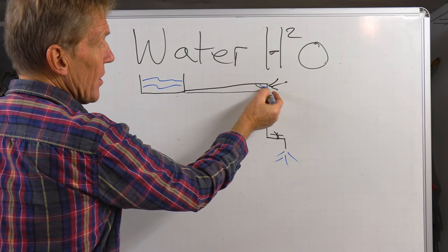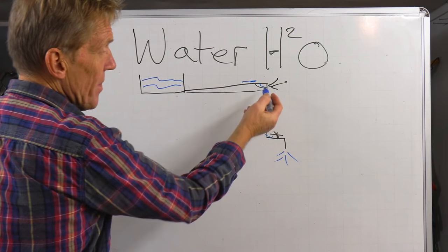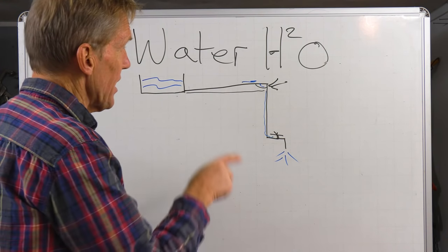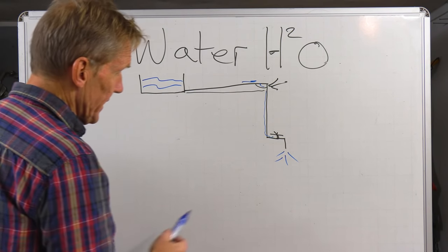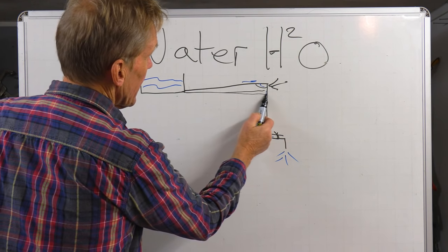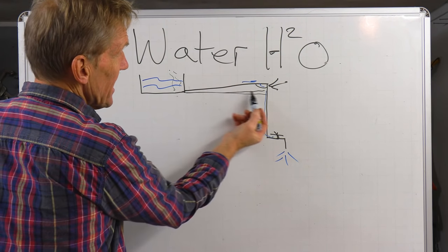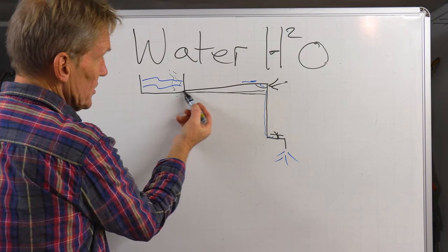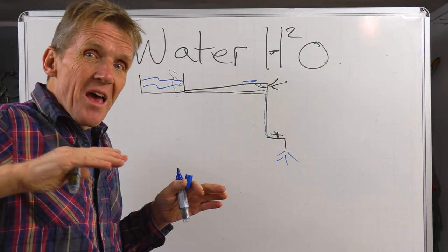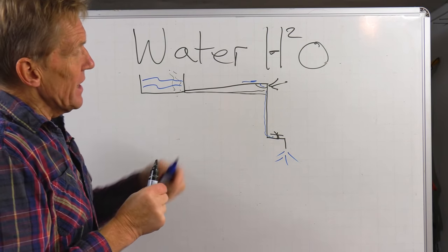But whatever it is, we have this little airlock here. So we've got water here. We might even have water there, but that water can't come out of a tap for exactly the same reason as I showed you in the glass. So the way we get round that is we put that pipe in so that any air in it vents towards the tank and just bubbles up out of there. Now, that means level will do, because it will just run along there, or downhill is even better, so that the pipes are rising back to the tank. And in that way, we avoid airlocks.